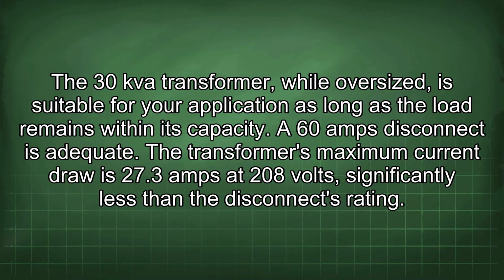The 30 kVA transformer, while oversized, is suitable for your application as long as the load remains within its capacity. A 60 amps disconnect is adequate. The transformer's maximum current draw is 27.3 amps at 208 volts, significantly less than the disconnect's rating.